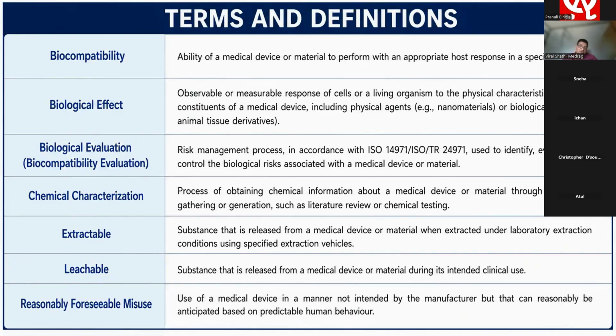The new standard also talks about identifying the foreseeable misuse of your device. Though you are claiming your device for use up to 24 hours, the clinical conditions and hospital healthcare scenarios are different. Suppose the infusion set: most manufacturers are claiming it for single use and for up to 24 hours only. But when we go to the hospitals, you can see the same IV set being used multiple times. They don't have time and they cannot replace the IV set periodically as per the instruction given in the IFU. In general practice that I have seen, an IV set is mainly used up to 3 to 4 days, or in some cases up to a week also.